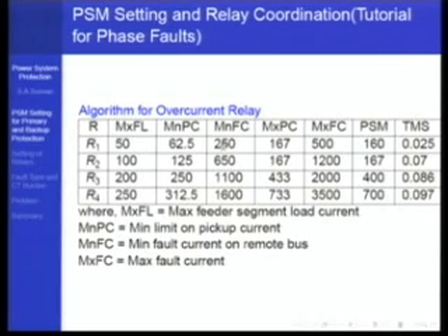Then the minimum fault current, which you will get from fault studies, is 250 amperes for R1 and 650 and so on. These are the minimum fault currents on the primary section of the feeder. Relay R1 has no backup responsibility. Its minimum fault current is 250 amperes. I said the pickup current should be less than 2/3 of this, so the upper ceiling on the pickup current comes out to be 2/3 of 250, which is 167 amperes.